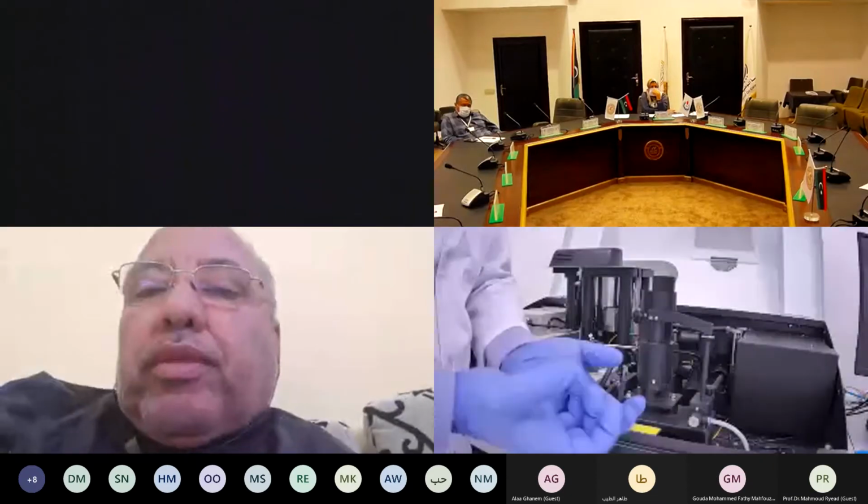In the same way, when you consider a dry module, you put your sample over here. This vibrator vibrates. It will fall onto this venturi, where it will encounter compressed air. That compressed air will push the powder particles towards the vacuum cleaner, and in between, the laser will fall on the samples and the light will get diffracted. And from that diffraction, we will get the particle size distribution.